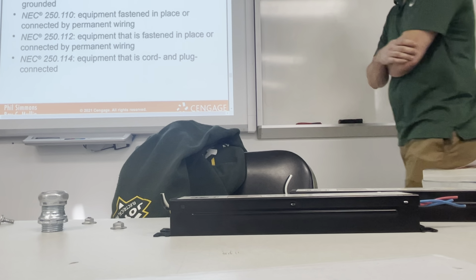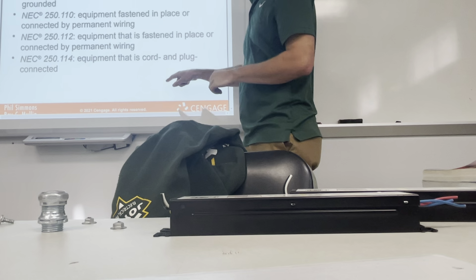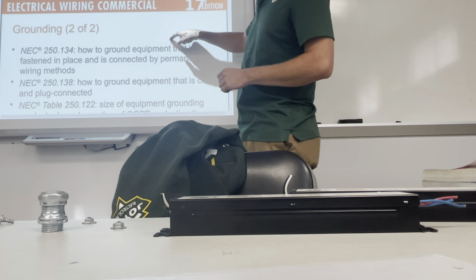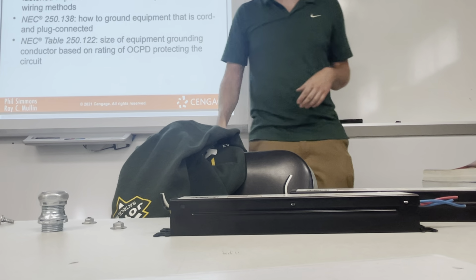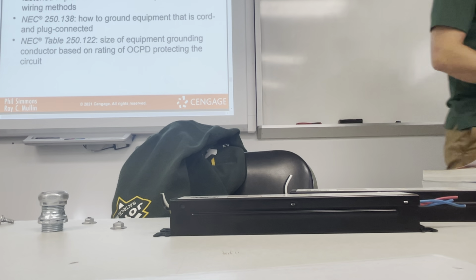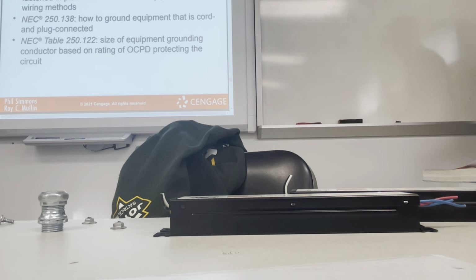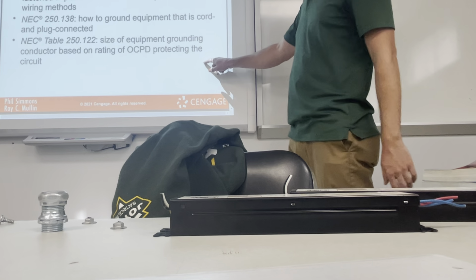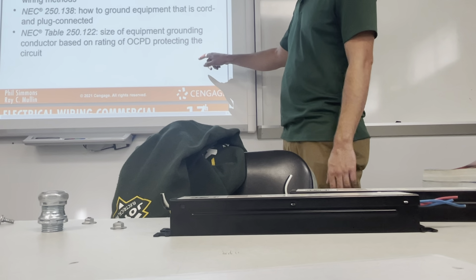But once again, if we go back to our grounding and bonding lesson, normally anything that's made by a manufacturer and is UL listed is going to have all the ground points, neutral points, hot points listed on it. So hooking these up isn't the hardest thing in the world if it's an appliance. If it pulls 30 amps at 240, then you're probably going to bring two 10s for power, a 10 for neutral, and a 10 for ground. And there's going to be ports on that unit to properly ground it because it was made and UL listed. So hooking up appliances isn't too bad. It's normally pretty well spelled out for you.